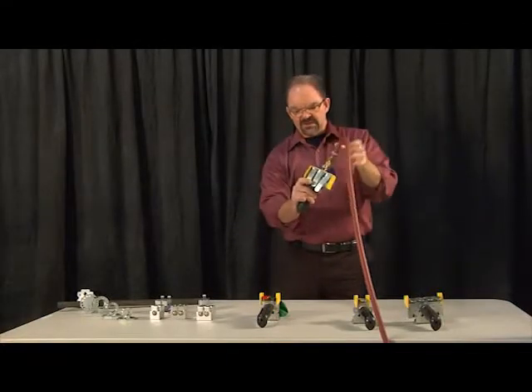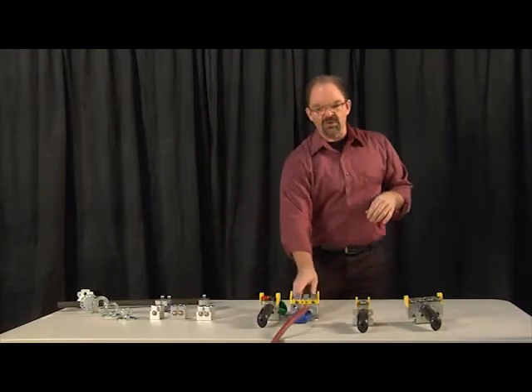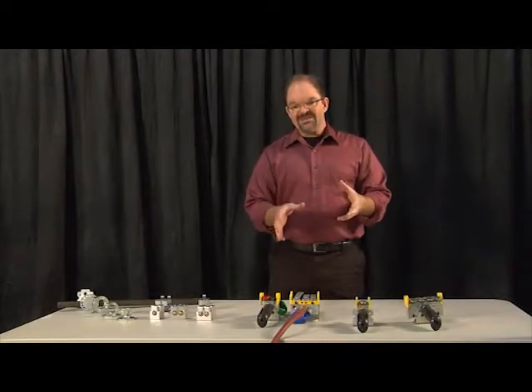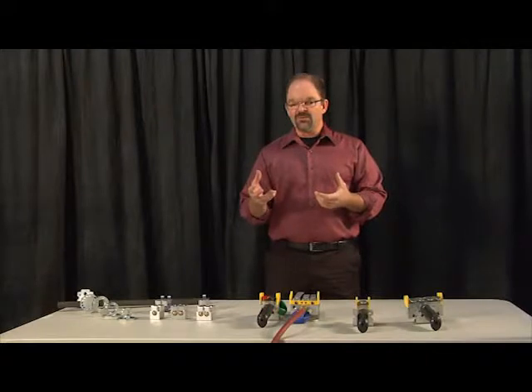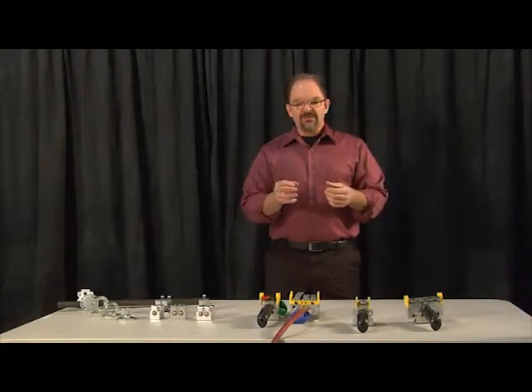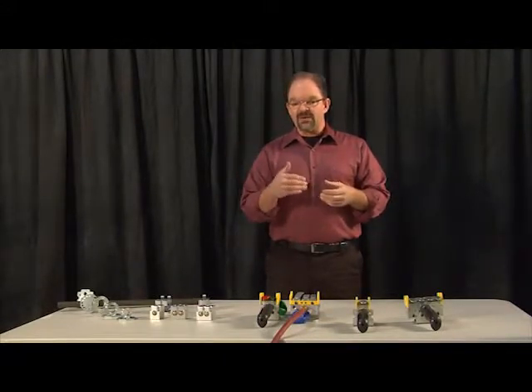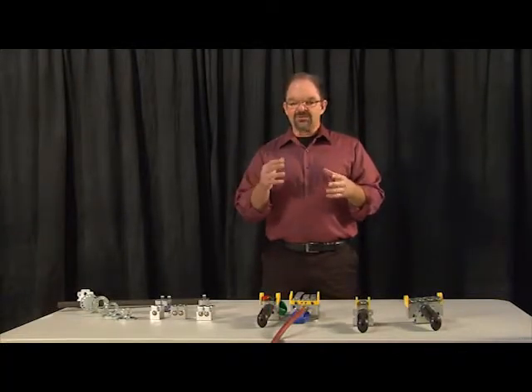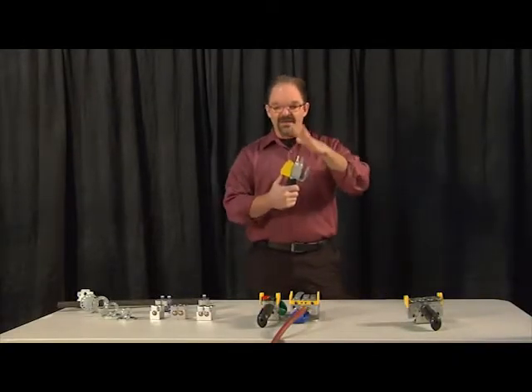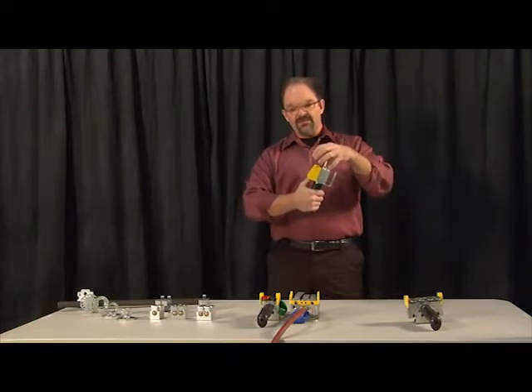The reason we have good depression force, very even depression force, and good control is because Gorbel designed these handles to be drop-in replacements with a significant improvement. We use a spool valve instead of the poppet valve that most competitors use. The spool valve does not increase in pressure with the increase in incoming air pressure. A poppet valve, incoming air pressure actually helps seat the valve, which means you have to overcome depression force. If this was a poppet valve and I cranked up the PSI to 100, I'd have to overcome 100 pounds of pressure before that poppet valve would open.